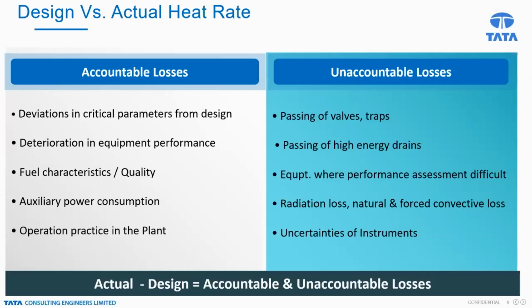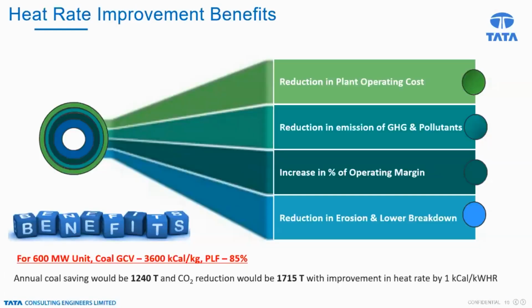So the accountable and unaccountable losses contribute to the difference between actual and design. We are very clear that we need to operate the plant at the specified or guaranteed heat rate. So what are the benefits we are going to get if we have a better heat rate, closer to the design or guaranteed heat rate? The first one is a reduction in the plant operating cost, because if you operate at the better heat rate, you will be using less coal because of the higher efficiency. So definitely it will reduce the plant operating cost.